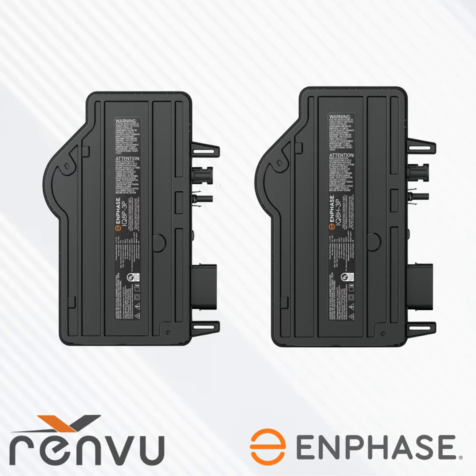We also have our Gateway Commercial 2. This is for site intelligence. The microinverters communicate with the commercial gateway, located at the PV subpanel. The inverters and the gateway communicate via power line communications, and that gateway gathers a ton of details about the PV system on a per-module basis. So you'll know what every single module is doing on your roof, how well or poorly it's performing, because we have module-level monitoring, since each module is paired with its own microinverter.